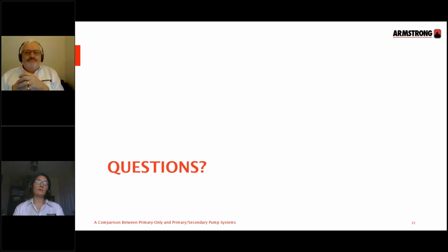Thank you. So it will depend on where you select. That's actually an important point, because when you design it, you have to think about that. So it's part of the design criteria now to change your way of designing, thinking that you can actually benefit from that parallel saving by selecting on the right side. So if you pick a smaller pump with a lower best efficiency, then you'll reach peak efficiency earlier than you would with a bigger pump with the best efficiency point way out to the right. Thank you both.